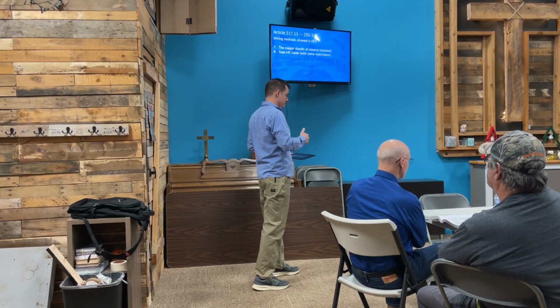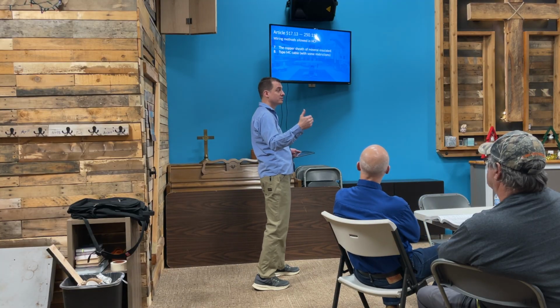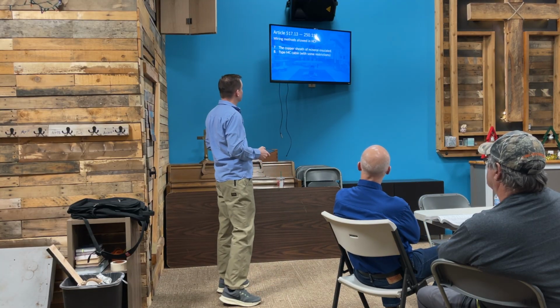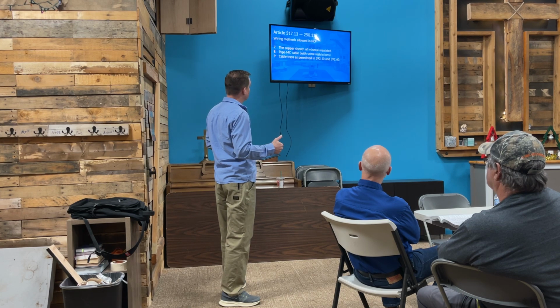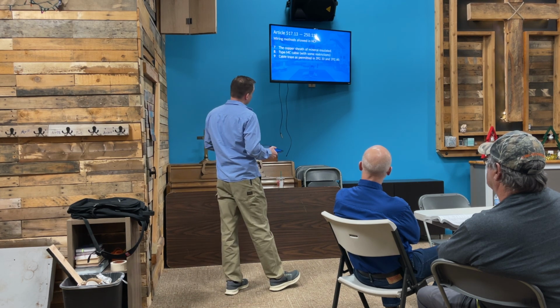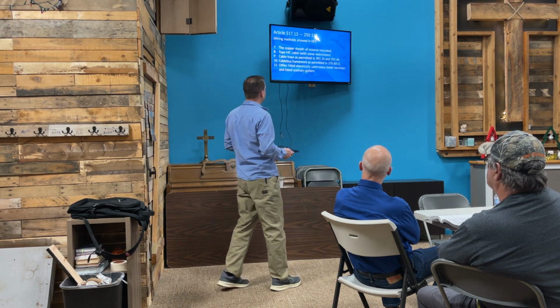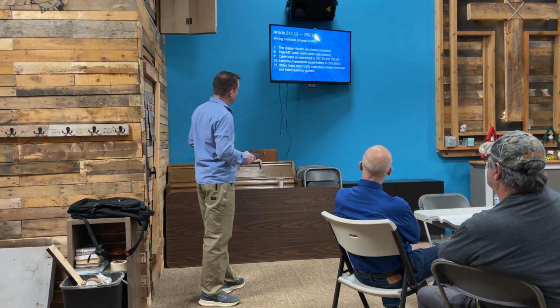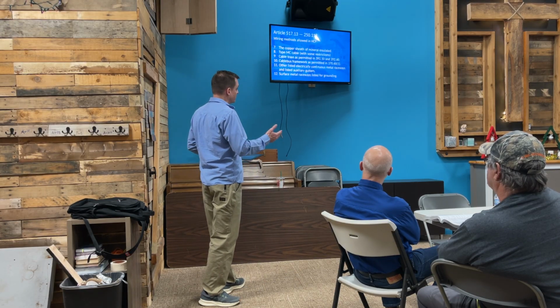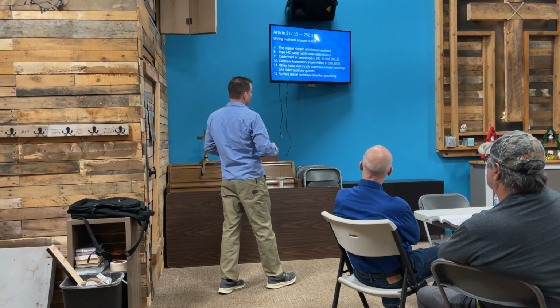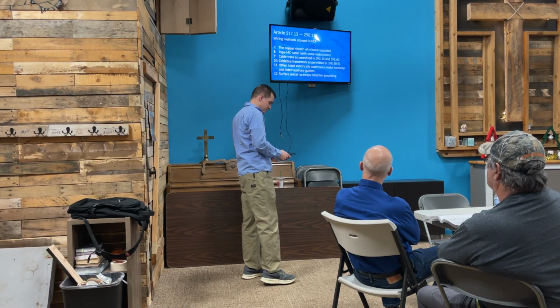MC cable, again with some restrictions - it's got to be health care rated MC, something I don't think you'd ever see, but it's in the list. Cable trays, cable bus, other listed metal raceways, and surface metal raceways listed for grounding - all those things would be permitted.